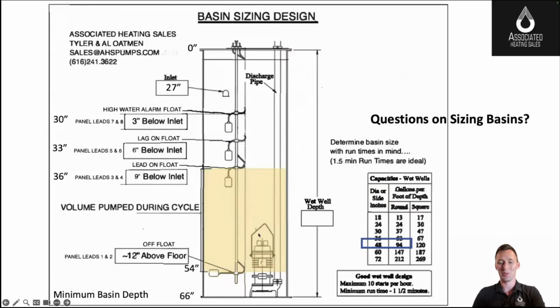Your calculation may be a little different, not as perfect, but I avoid public math this way when I do the presentation. So I have 1.5 feet. If I had 2 feet here, I'd be even more excited. That way, if the inlet came in a little lower than expected in the field, you have a little wiggle room. These pumps don't short cycle and they don't burn out early. You put a lot of wear on a pump if you short cycle it.